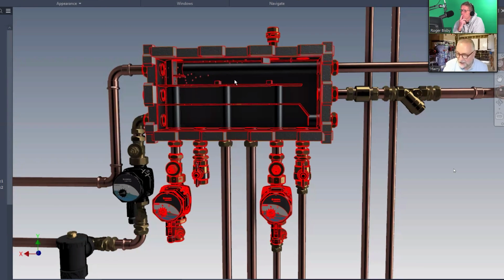Yeah. So anyway, the other thing I told you, if I have a barrel of water and I put a pipe leaving the top of the barrel at the side and coming back for the bottom of the barrel at the side, and if I put my pump pumping into the barrel and it's a 10-meter pump, say, in that system I have 10 meters of head pressure between the pump and the barrel. But if I pump from the barrel out and it goes around the system, I have 10 meters of pressure all the way around the system.